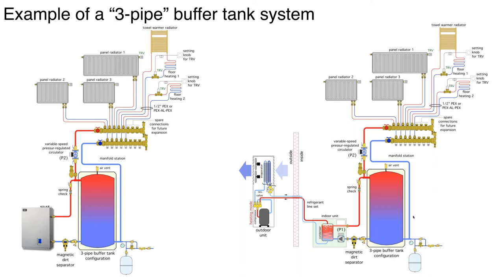Here's a couple of example systems. The one on the left is using a boiler. So we can set up a ModCon boiler and go into a three-pipe buffer as shown. We've got an air separator — I'm showing it on a vertical line just to show there are options — and we're going up to a nice array of panel rads, maybe some floor heating circuits and a towel warmer. We're using home-run circuits with half-inch tubing of any sort, and we've got a manifold. What really caps this off is a variable-speed pressure-regulated circulator. That circulator can be set for constant differential pressure, and it'll simply ramp up and down as these thermostatic valves open and close. We actually talked about this kind of distribution system on our first installment of these webinars — it's a simple system that works really well.